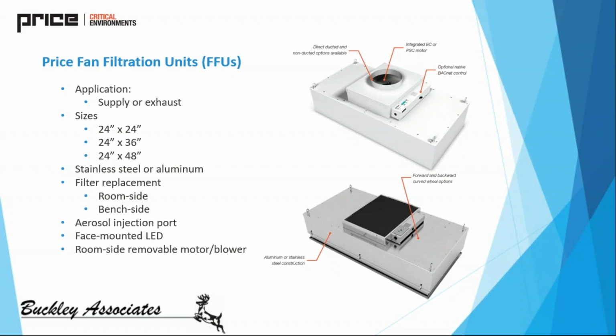One of the most recent updates, I don't know if you all have seen this before, is that Price has added a little optional LED indicator in one of these, so anybody can really see in the room whether it's time to replace the filter without having to regularly check the filter cleanliness. HEPA filtration can be verified, so there's a built-in aerosol port in here. At commissioning, we can verify that we have proper HEPA filtration via that aerosol port. It's easy access, it flips down, and it's built into every one of these.